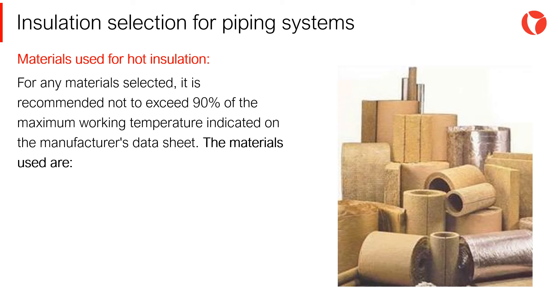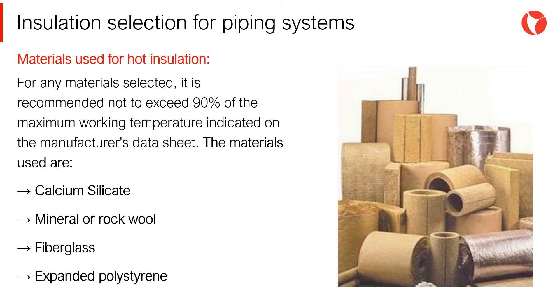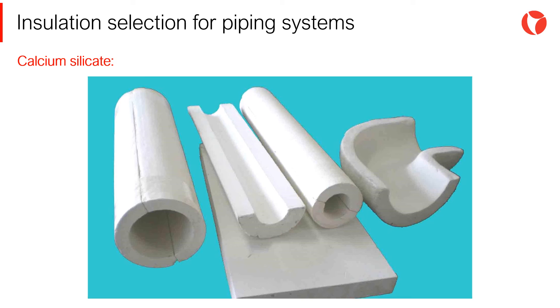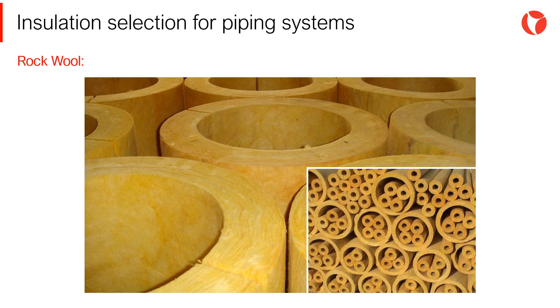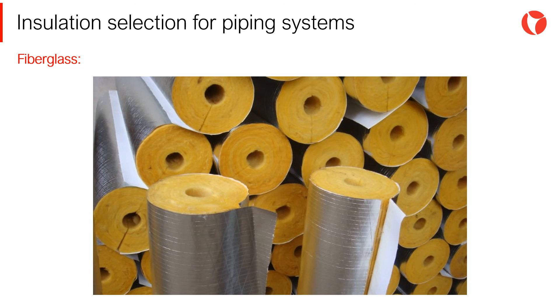Most materials used are calcium silicate, mineral or rock wool, fiberglass, and expanded polystyrene. One of the most widely used ways to insulate pipes are preformed cylindrical sections, which facilitates installation considerably. On the screen we see an example of calcium silicate as an insulating material, an example of rock wool — perhaps the most used insulating material for all piping systems in industrial plants — and an example of preformed sections of fiberglass.